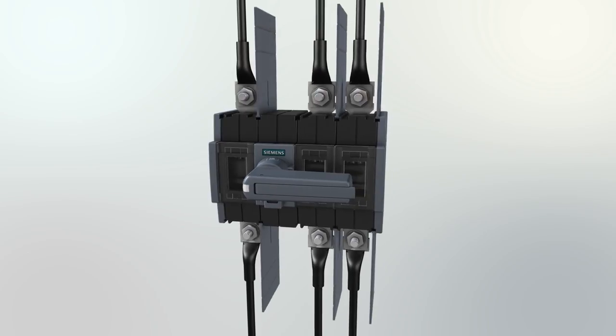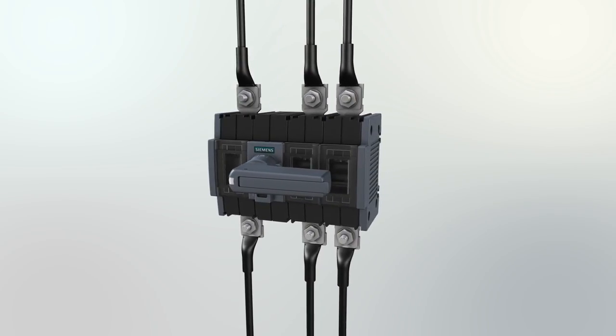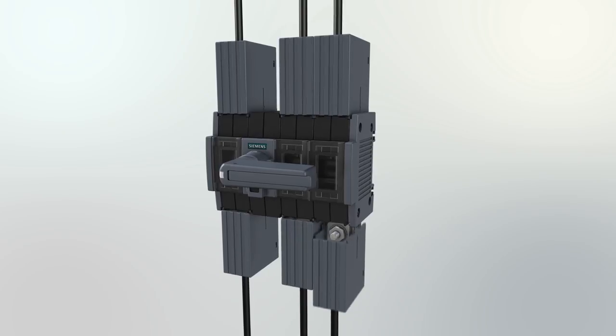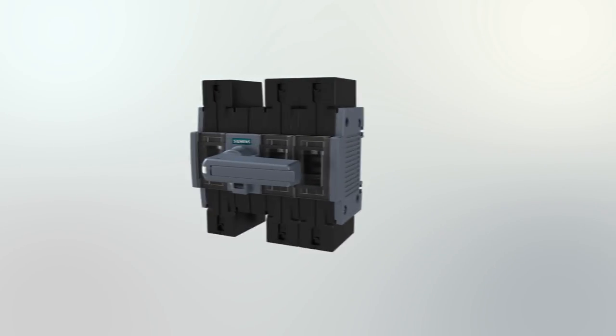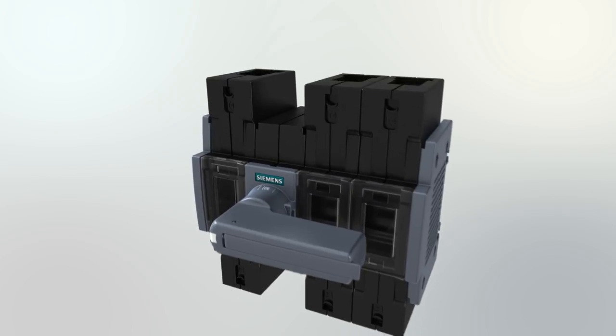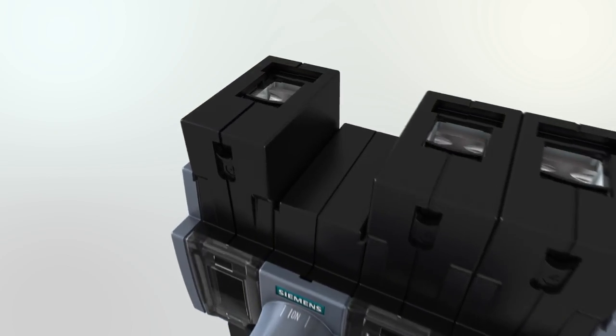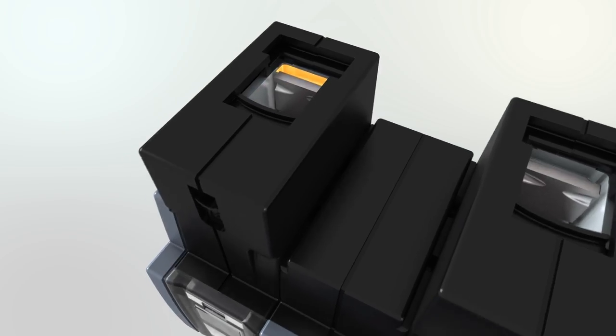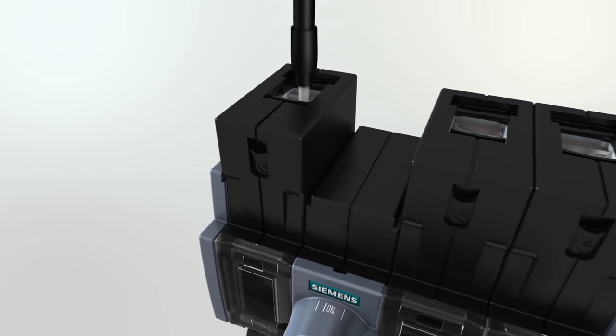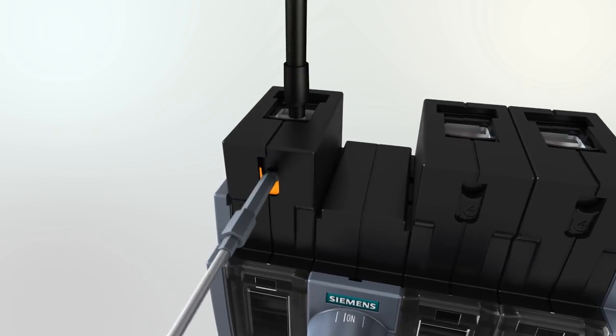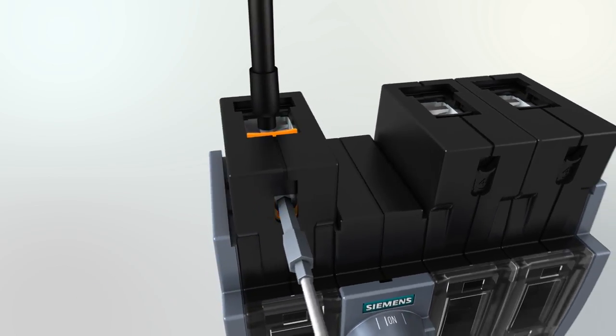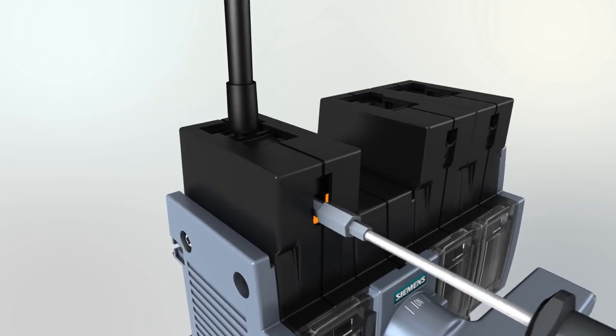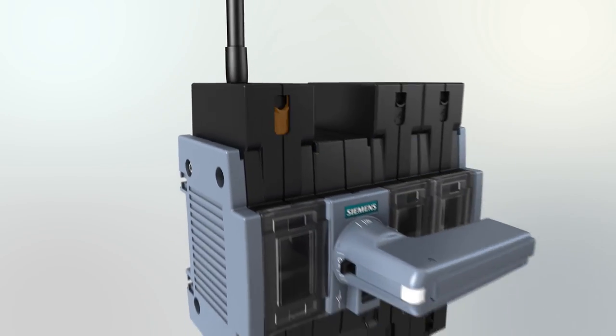In order to protect all terminals against contact, you can use connection covers as well. Variants up to 160A can also be connected via box terminals for stripped conductors. The special box terminal is suitable for circular conductors and flat cables, or for both at the same time. The terminal is covered for greater protection. This covering automatically returns to the starting position once the terminal is closed.